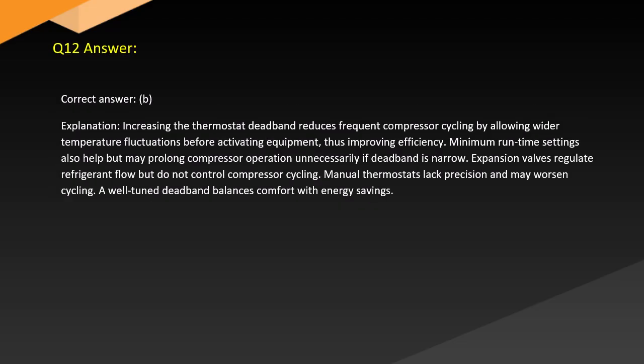Answer. Correct answer, B. Explanation. Increasing the thermostat deadband reduces frequent compressor cycling by allowing wider temperature fluctuations before activating equipment, thus improving efficiency. Minimum runtime settings also help but may prolong compressor operation unnecessarily if deadband is narrow. Expansion valves regulate refrigerant flow but do not control compressor cycling. Manual thermostats lack precision and may worsen cycling. A well-tuned deadband balances comfort with energy savings.